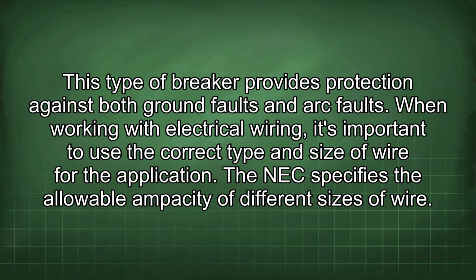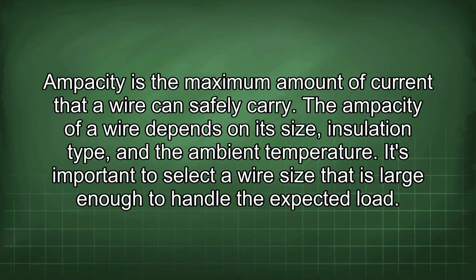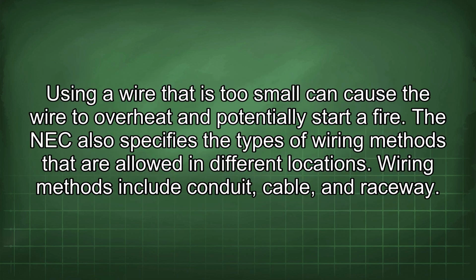When working with electrical wiring, it's important to use the correct type and size of wire for the application. The NEC specifies the allowable ampacity of different sizes of wire. Ampacity is the maximum amount of current that a wire can safely carry. The ampacity of a wire depends on its size, insulation type, and the ambient temperature. It's important to select a wire size that is large enough to handle the expected load. Using a wire that is too small can cause the wire to overheat and potentially start a fire.